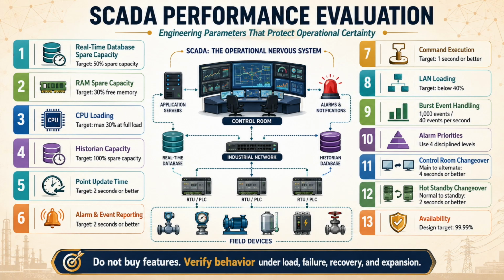The third engineering parameter is CPU loading, because server processors carry real-time database processing, protocol drivers, alarm processing, historian compression, display serving, scripts, calculations, security services, redundancy heartbeat, reports, operating system processes, remote access, and background services. A server running at 65% CPU during normal operation may look acceptable until alarms burst, communication links recover, historian backfill begins, clients reconnect, and redundancy synchronization occurs simultaneously.